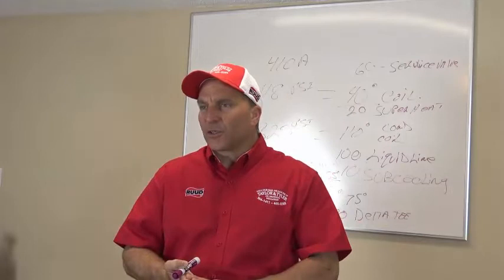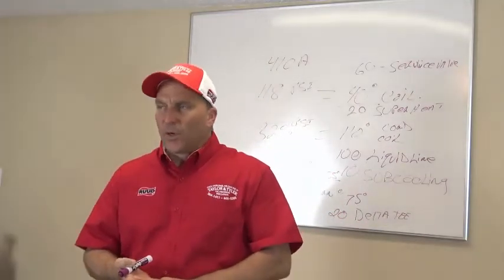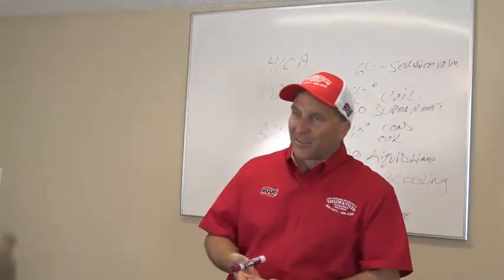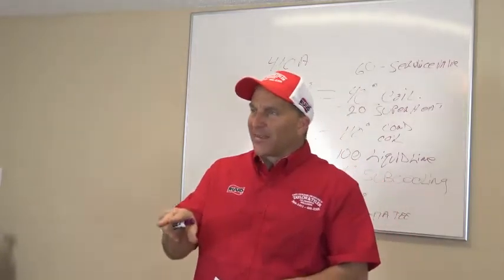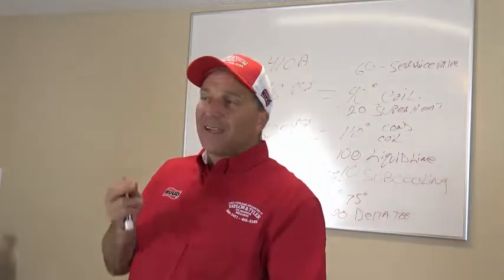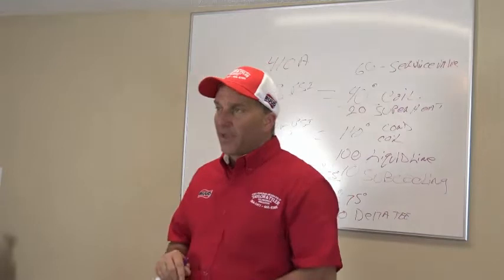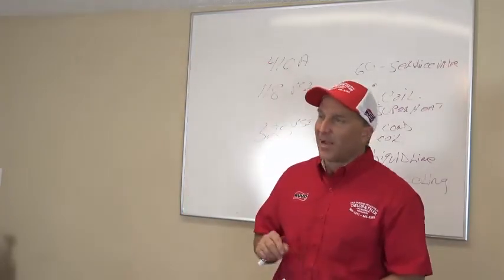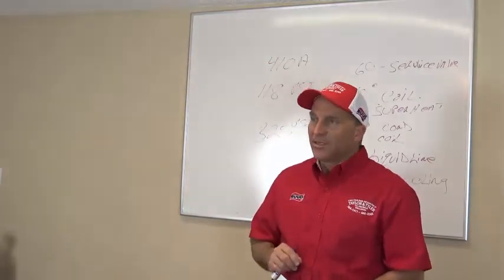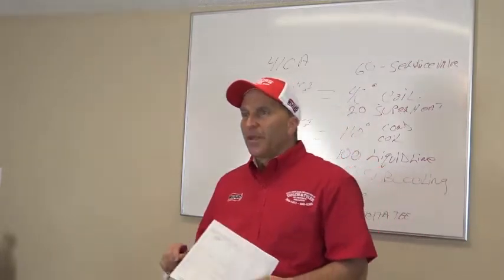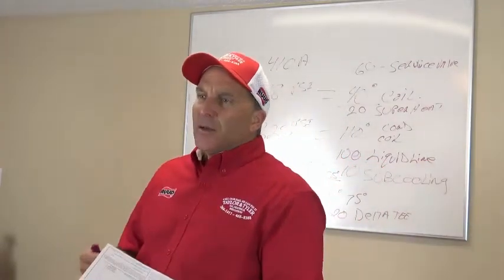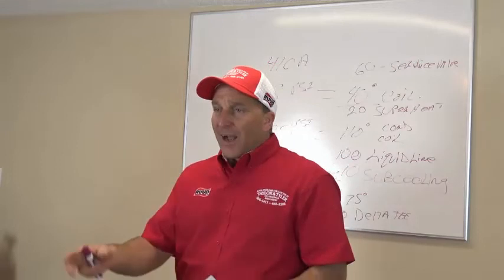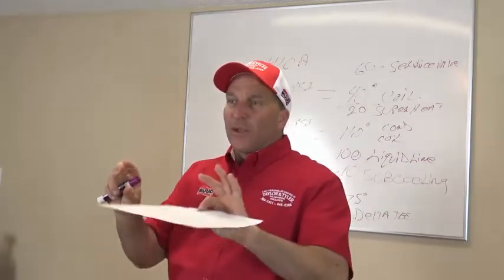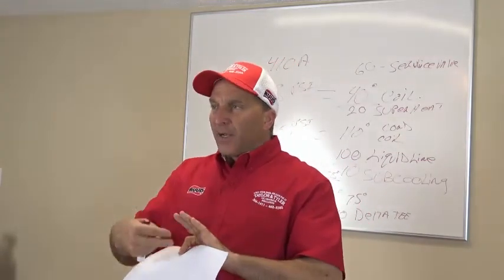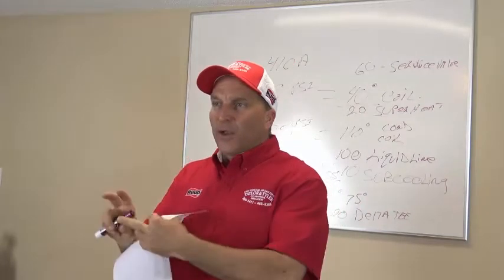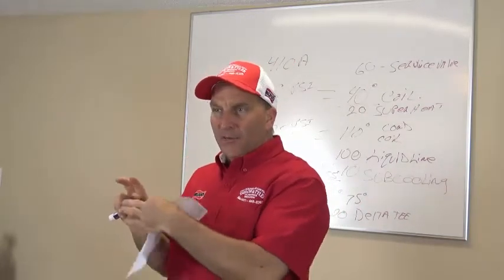So anytime you're servicing the system or doing a PM, you need to look at that contactor. If there's a cover over the contactor points, use your screwdriver and take the cover off and look at the points. It may be burned up all inside of there, and you may not know it. Look inside of it and see if it's all burned up. Then make a recommendation. Sir, here's the contactor that's in your system. Here's a brand new one. You see how this one's all pitted up and burned up in your points? Your brand new one, how everything's nice and clean and you have good connections on it.